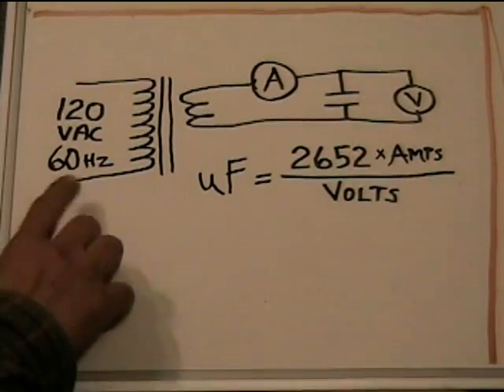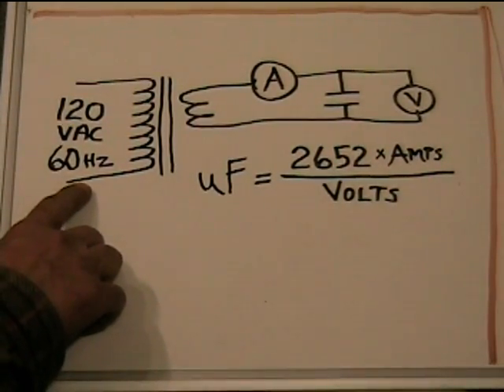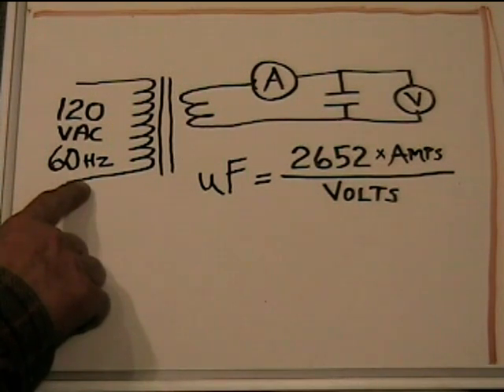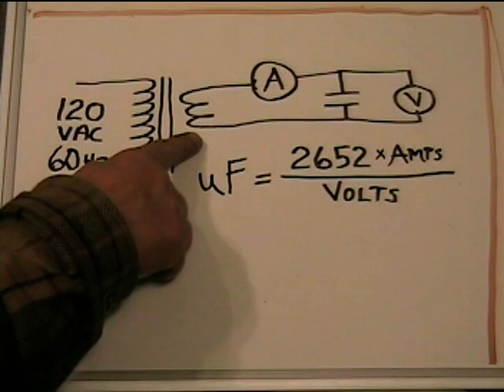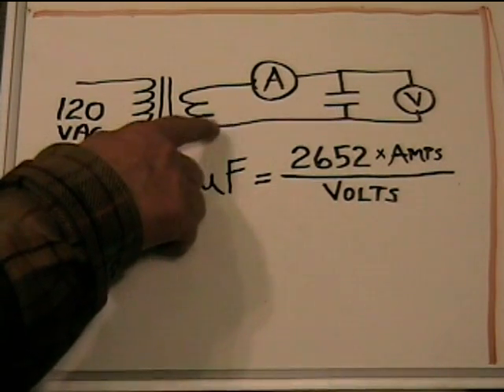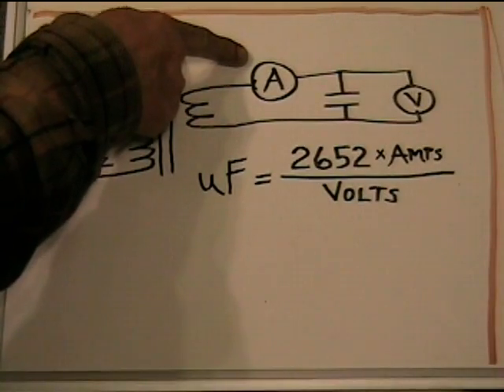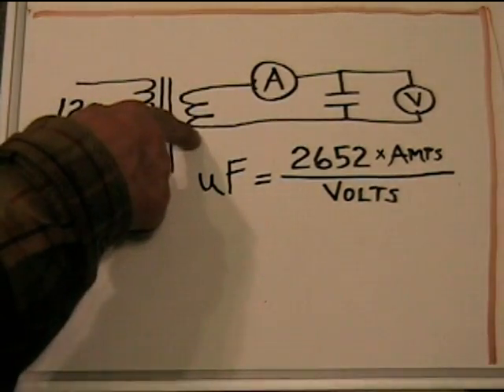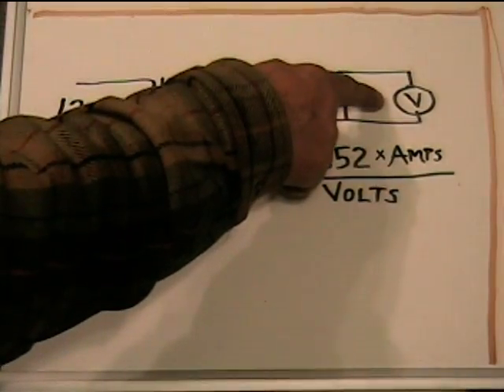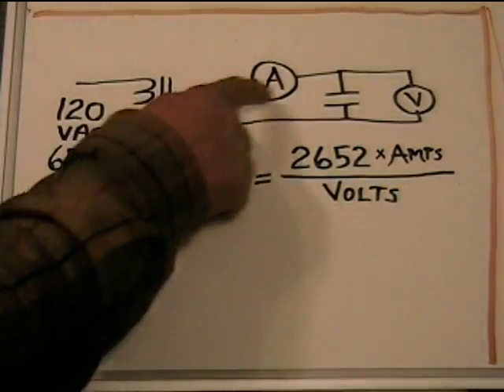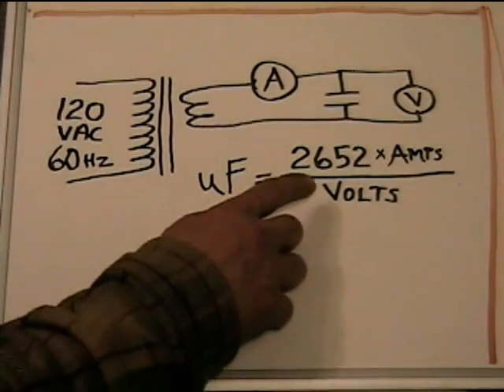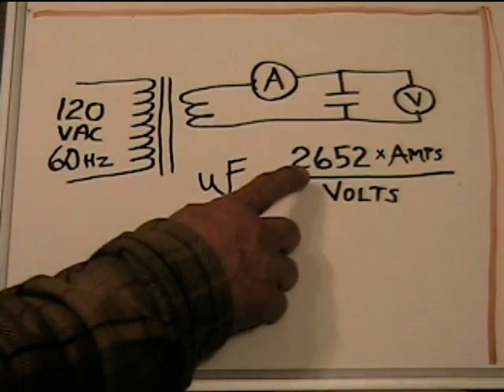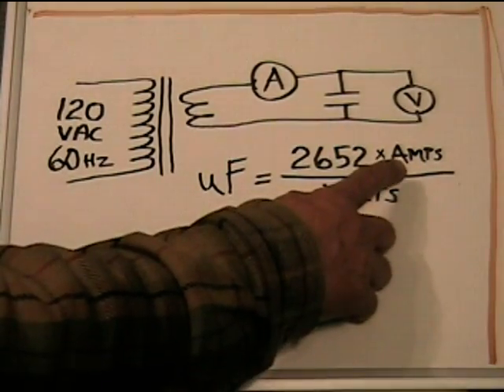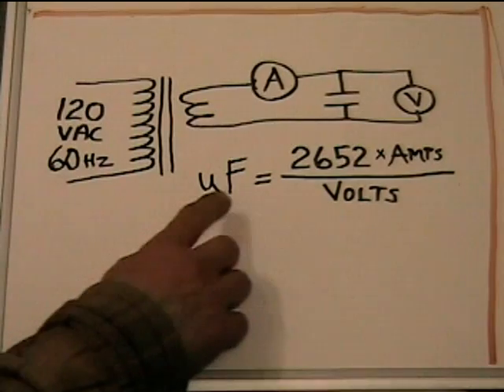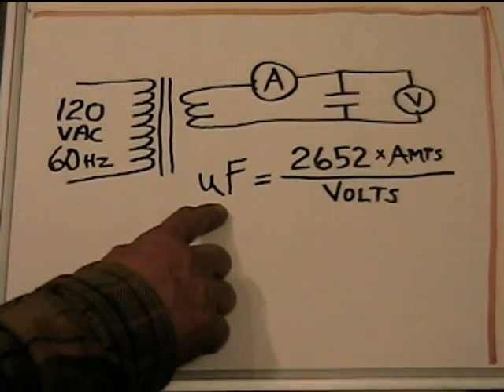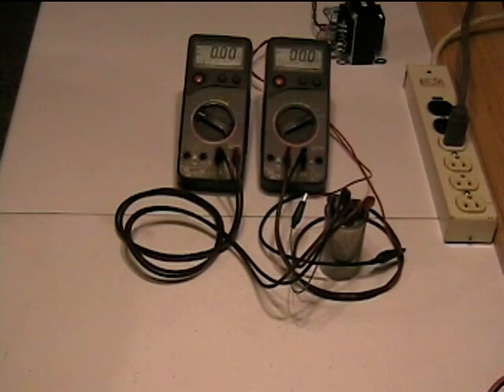Schematically, it looks like this. I have the transformer input, 120 volts AC at 60 Hertz. Frequency is important. Secondary of the transformer, anything from 12 volts AC up to 30 volts AC, so it's safe to work with and we're isolated. Through the ammeter, through the capacitor, back to the transformer, and then across the capacitor we have our voltmeter. Turn on the power just momentarily to get an ammeter and a voltmeter reading, turn the power back off, and then we plug the values into our formula. We have a constant, which is 2652, times the amperage divided by the voltage. The result of the formula gives you capacitance in microfarads. All very easy. So let's turn it on and do our math.